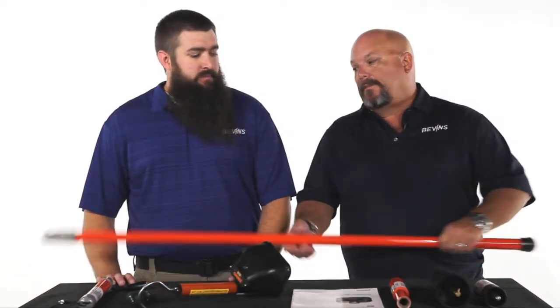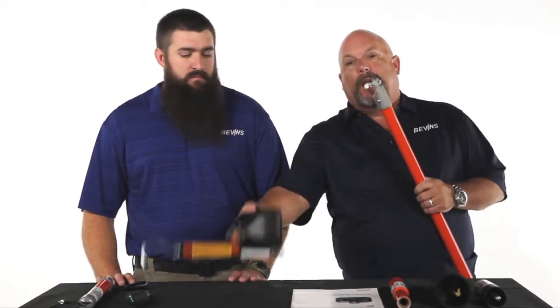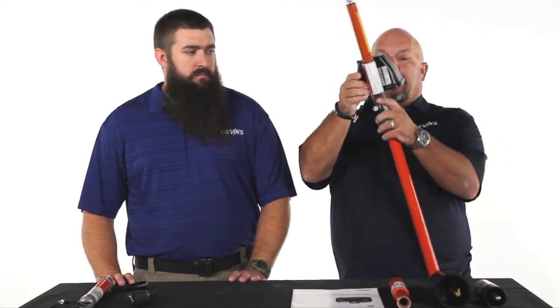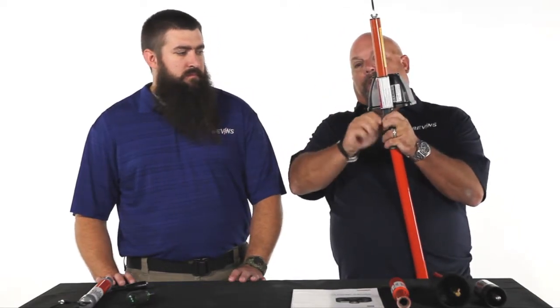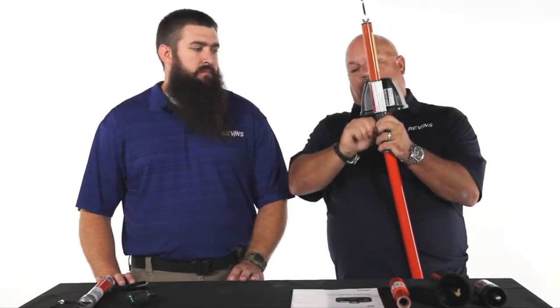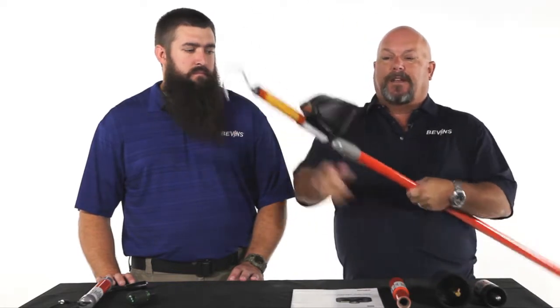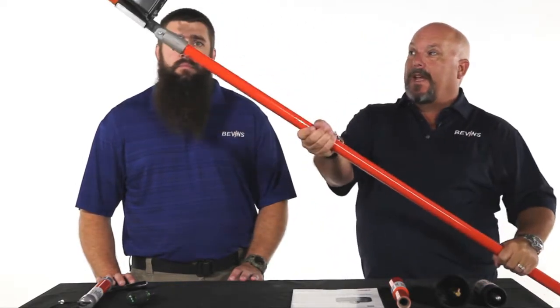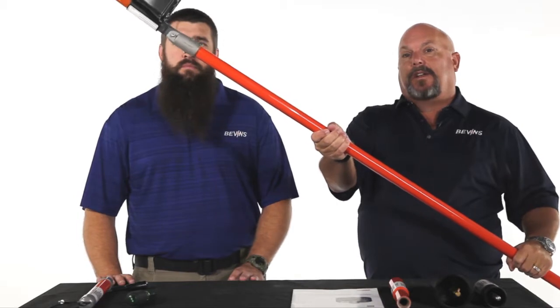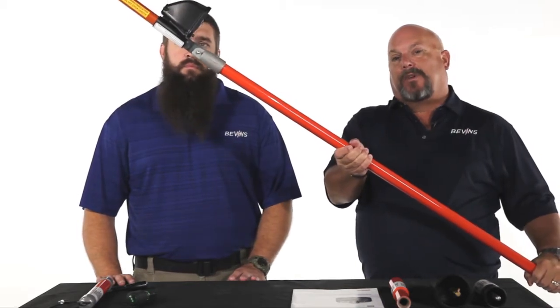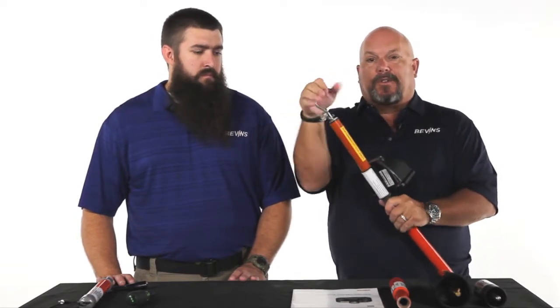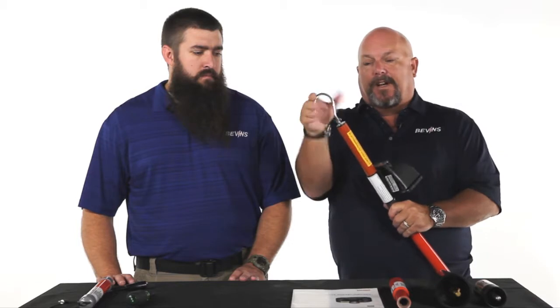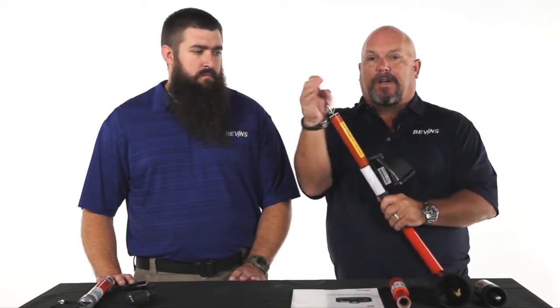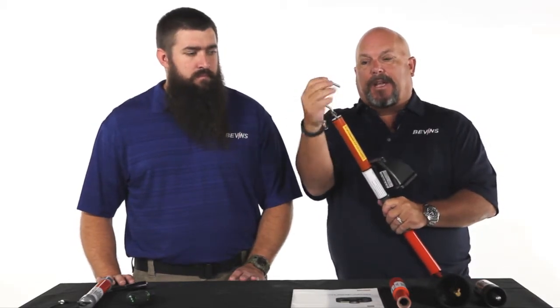As always, with our testers, please use your MAD, your minimum approach distance. Very important for your safety. Best thing to do is use the universal head, tighten it down, middle span is your best reading. Closer you are to ground, the higher the reading. That's for your overhead. You can undo the hook, and we have adapters for underground. Very, very important that you use the appropriate underground bushing adapter or elbow adapter.